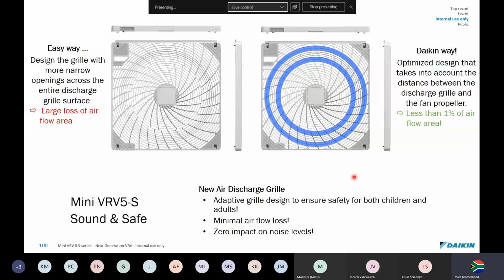Another advantage is the design grill. On previous designs, there was a large loss of air in the flow area. If you look at the way these vanes have been staggered, Daikin now have optimized that design. It takes into account the distance between the discharge grill and the fan propeller, and they've improved the air discharge, so there's less back pressure on the fan. They've also had to adapt the grill design to ensure safety for children and adults, where they put their fingers through.